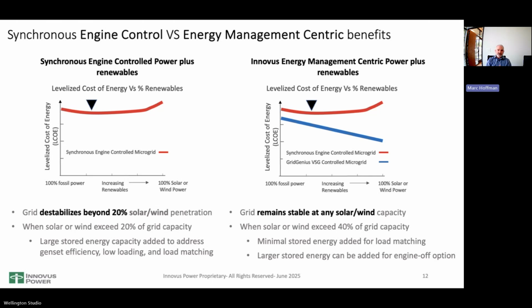So what happens is either people stop adding solar and wind to synchronous systems because they already know about the 20% problem, or if they didn't know about it - and that happened in many communities in Alaska 10 to 12 years ago - they kept adding more wind power and realized they had to curtail it. You'll see a case example of that shortly. So now you've added all that cost of generation, but you're not able to take advantage of it because you're having to curtail 60, 70, whatever percent of its capacity, since your synchronous gensets controlling the power quality for that grid can't stay stable. At some point, your cost of power starts to flatten out.